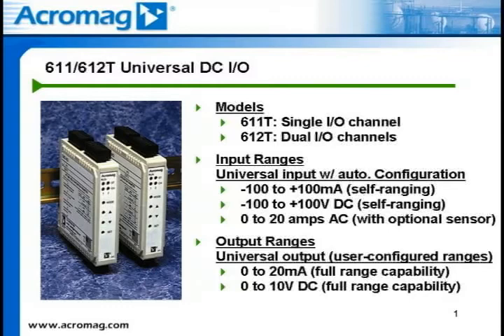Universal input ranges can accept either a minus to plus 100 milliamps DC signal with full range capability, with a minimum recommended span of 4 milliamps DC, or a minus to plus 100 volts DC signal with full range capability, and a minimum recommended span of 1 volt DC. A 0 to 20 amps AC signal can also be monitored utilizing Acromag's AC current sensor.